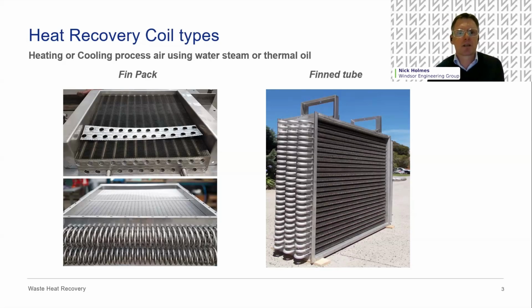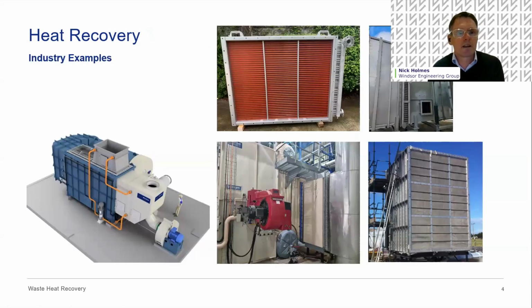So really today is just about some examples of what can be done, what we have done in recent years. There's just an array of different photos here to put it into perspective. So in the middle at the top is a 30 megawatt economizer for a boiler. The one below that is a primary and secondary economizer application. We'll go into more detail on that one in a couple of weeks, if you're sitting in on the boiler specific session. This is a large steam air heater, typically used in a powder spray dryer where they need a lot of high temperature air for the process. So you need 200 odd degrees in air temperature, so you need high pressure steam to generate that hot air. But you can put a heat recovery coil in the exhaust, and we'll cover later how that can reduce the steam demand.